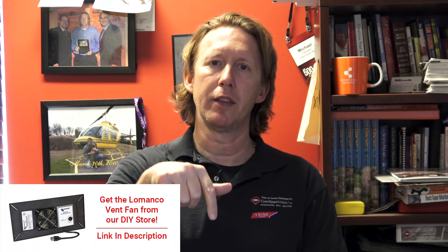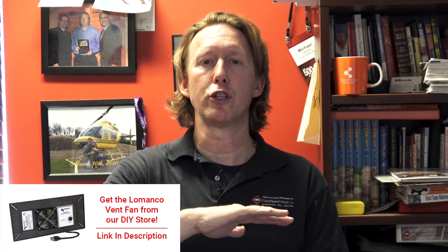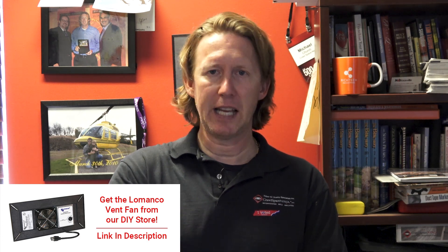Okay, David in North Carolina. Here's the thing about ventilating a crawl space and the sizing. If you are installing vent fans in an open crawl space where you're not running a dehumidifier and you're not sealing the vents, there is a ratio that Lomanco has. I'm going to put a link to the DIY page where the Lomanco fan is so you can check out the owner's manual if you're going to use a fan to ventilate the crawl space and not install a dehumidifier.